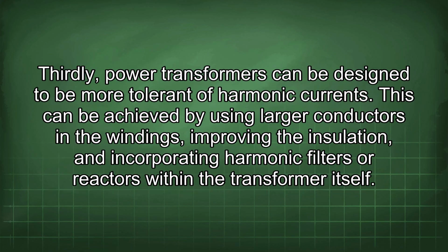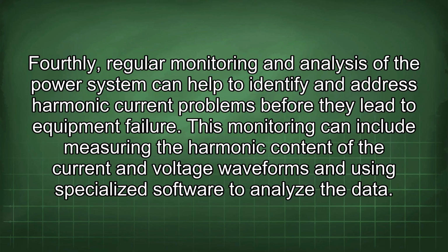Thirdly, power transformers can be designed to be more tolerant of harmonic currents. This can be achieved by using larger conductors in the windings, improving the insulation, and incorporating harmonic filters or reactors within the transformer itself. Fourthly, regular monitoring and analysis of the power system can help to identify and address harmonic current problems before they lead to equipment failure.